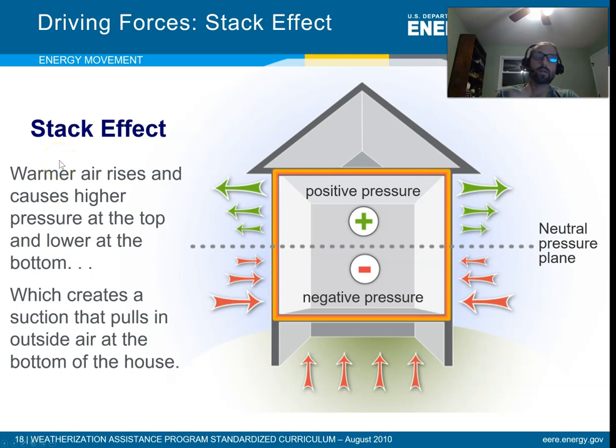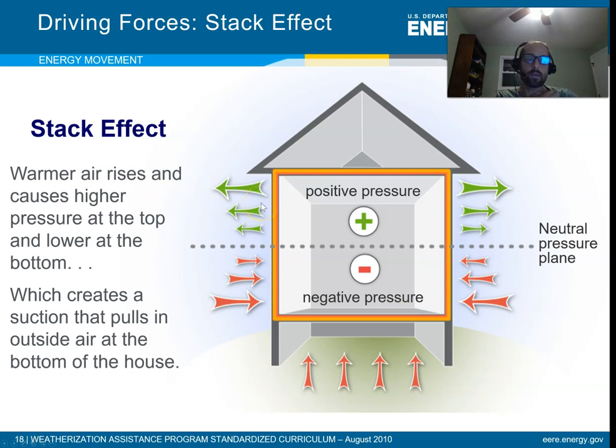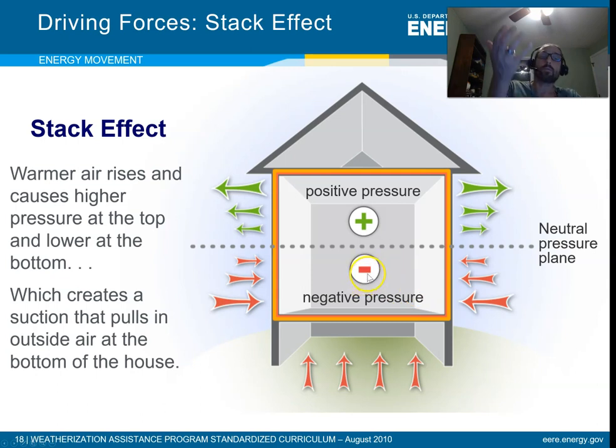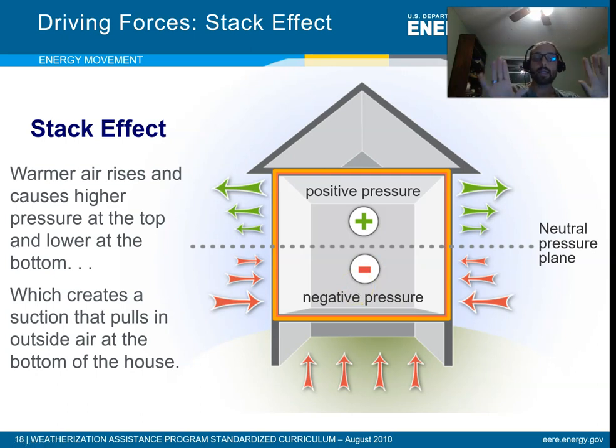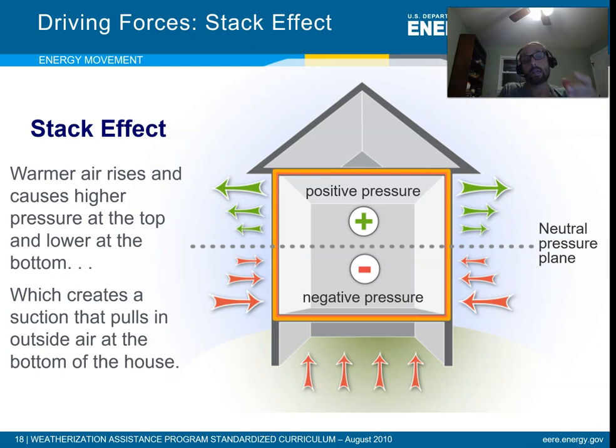The stack effect is pretty straightforward and happens primarily in the heating season. Warm air rises, pushing air toward the top of the building. Any time you force air into an area, it increases air pressure. Conversely, any time you pull air away from an area, it drops the pressure there.